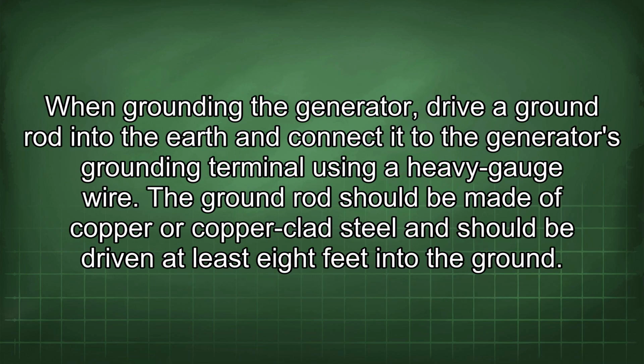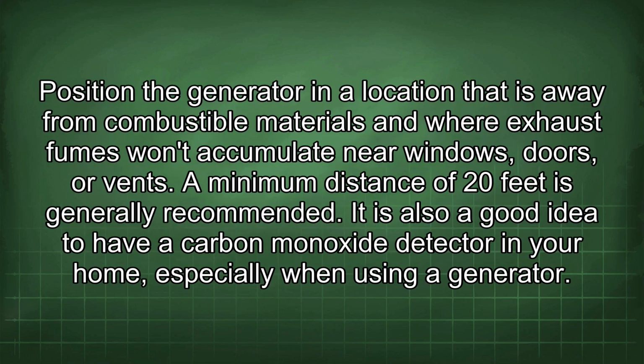When grounding the generator, drive a ground rod into the earth and connect it to the generator's grounding terminal using a heavy gauge wire. The ground rod should be made of copper or copper-clad steel and should be driven at least 8 feet into the ground. Position the generator in a location that is away from combustible materials and where exhaust fumes won't accumulate near windows, doors, or vents. A minimum distance of 20 feet is generally recommended.